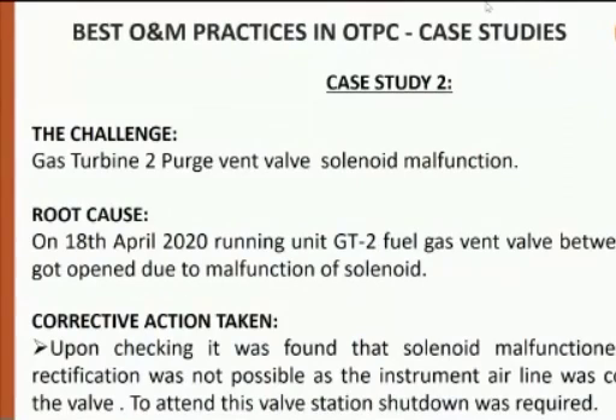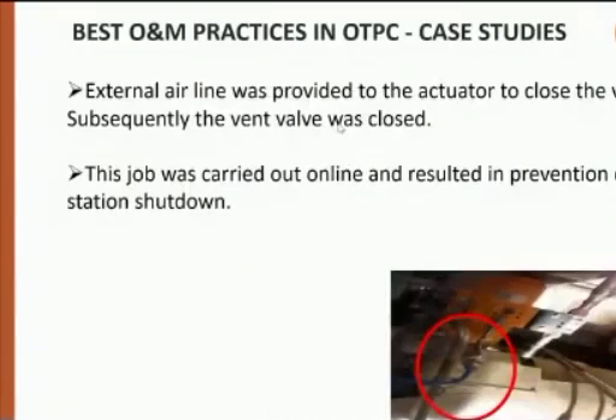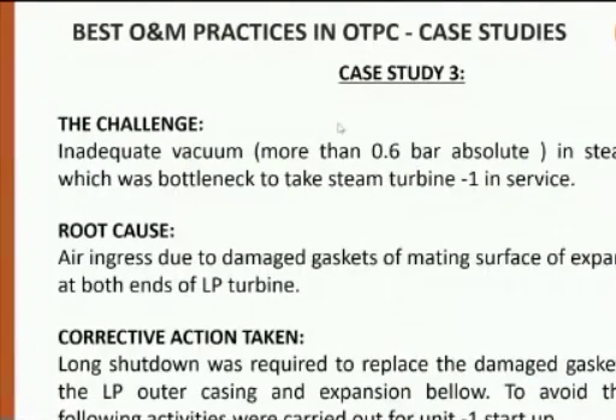So what we did was give a supply of air from an external source to the valve so that it gets closed, and we could remove the faulty solenoid and replace it with a healthy solenoid, and put this purge valve back in the normal operating mode. So the job was done very successfully, and it avoided a shutdown of almost 8 to 10 hours. So that was one case study we have done, and now another, case study number 3.